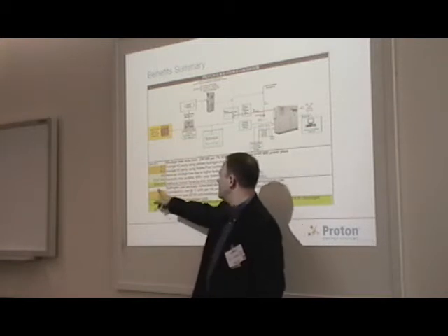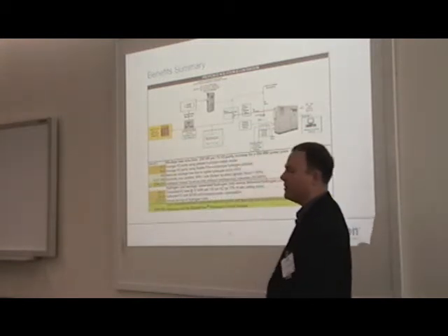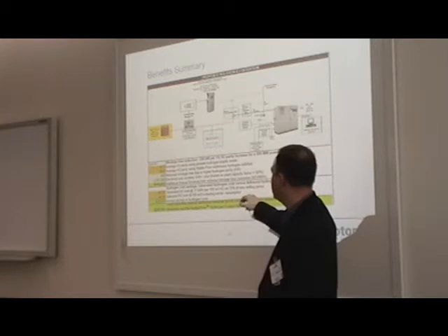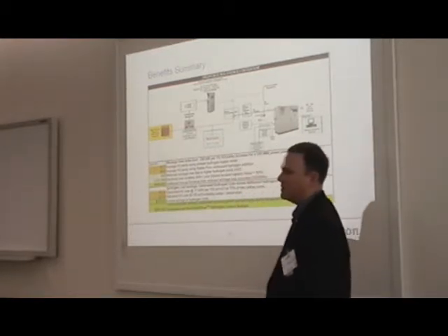So the electricity loss avoided for a year is a little over 3,500 megawatt hours. Considering a $45 per megawatt hour sale price, you can see very close to $160,000 in savings. Here's the windage loss alone for this facility.